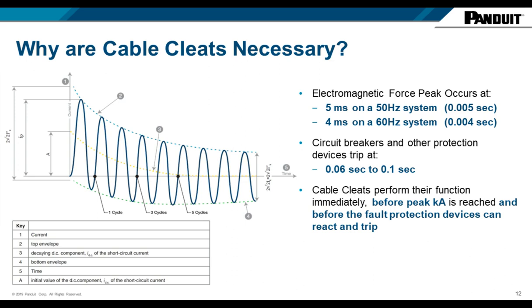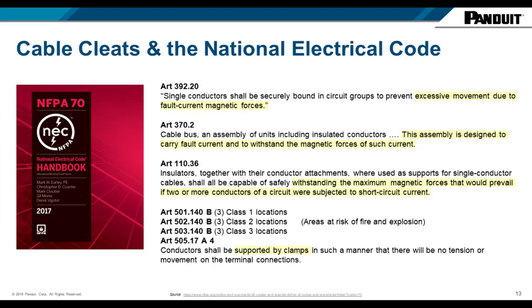Often we see on a cable specification one or three seconds for a short circuit withstand — that is purely about the cable's heat and current capacity (I²T). We worry about five milliseconds regarding the performance of the cable cleats.